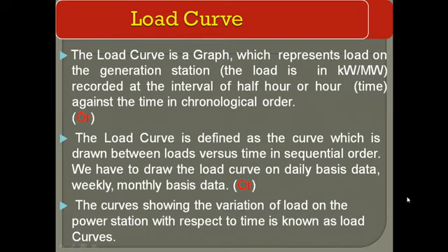Load curve. It is very important. Load curve is a curve which represents load on a generation station. The load is in kilowatt or megawatt, recorded at the interval of half hour or hour against the time in chronological order. In another way, we can say it is the curve which is drawn between load versus time in sequential order. We have to draw the load curve on daily basis data, weekly, or monthly basis data.